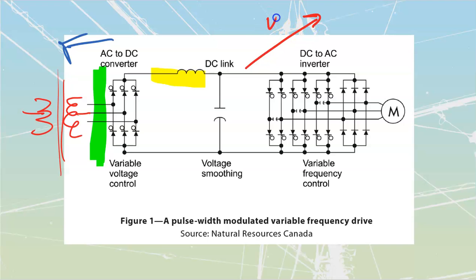Anytime that you do run a motor, by the way, at a reduced speed, remember that V/F line had to go up. We kept those things the same. If I'm keeping my V/F constant on my motor, I'm going to have a reduced amount of current. I'm still going to get torque out of that motor at that reduced value of voltage, but I'm going to have a reduced amount of current, which means that I do need to have those overloads programmed in so that my VFD understands and can be responsive to it.